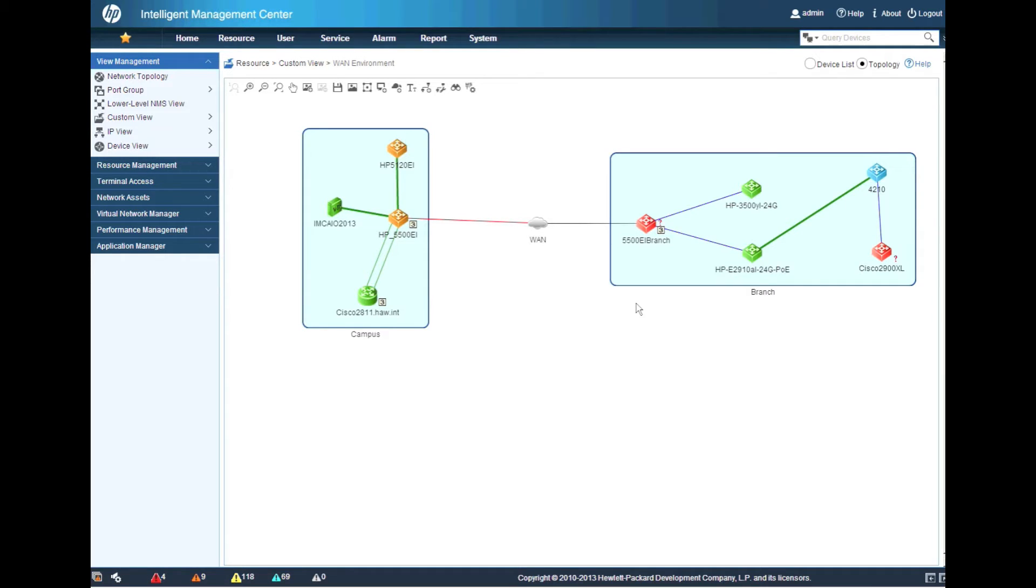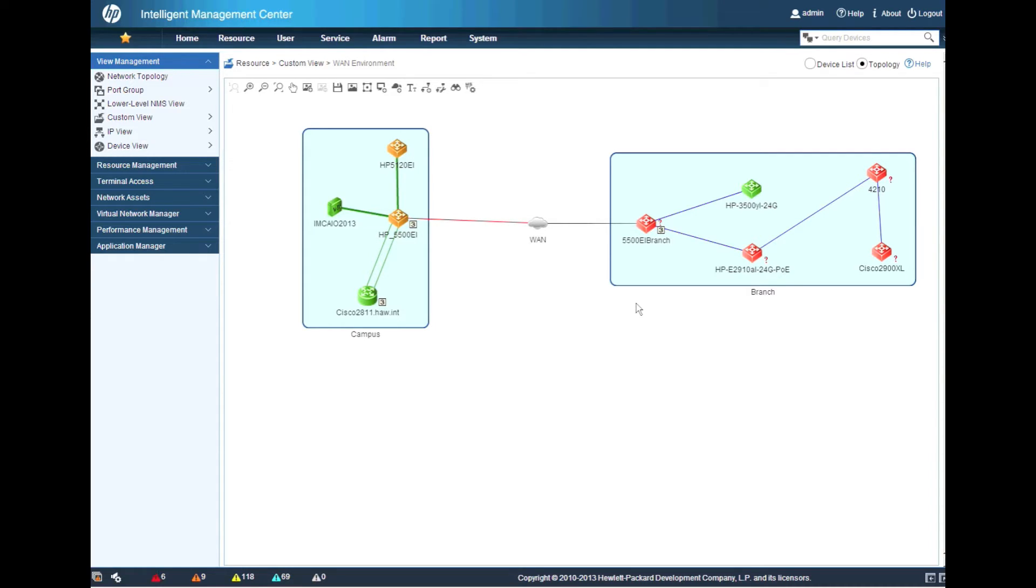So this is based on the default polling interval which will poll the device every 60 seconds. So at some point in that minute, depending on where we hit the polling interval, we will identify all these devices going down, usually within the first 30 seconds. And we'll wait for the last one to go down here.